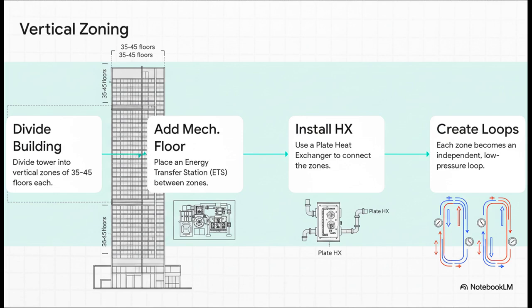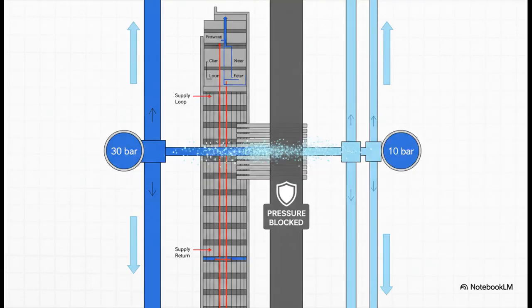And the undisputed hero of this entire strategy is the plate heat exchanger. Seriously, think of it like a thermal gatekeeper. It lets the cold from the main water line pass through to the next zone's loop, but it physically blocks the pressure from crossing over. Each zone is totally isolated, hydraulically speaking, and just like that, our 30-bar pressure problem, gone.